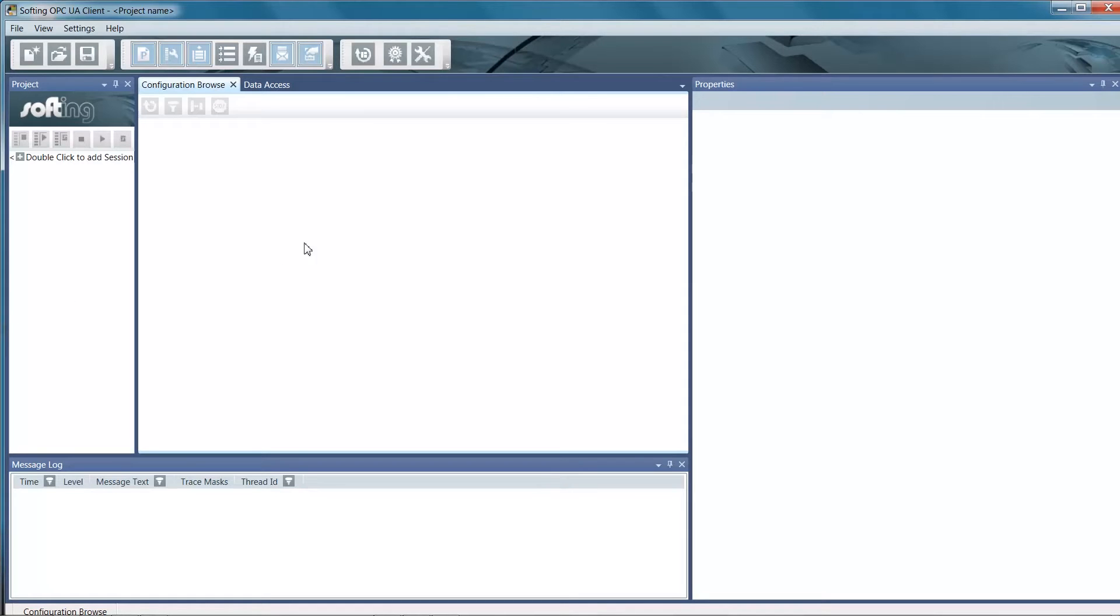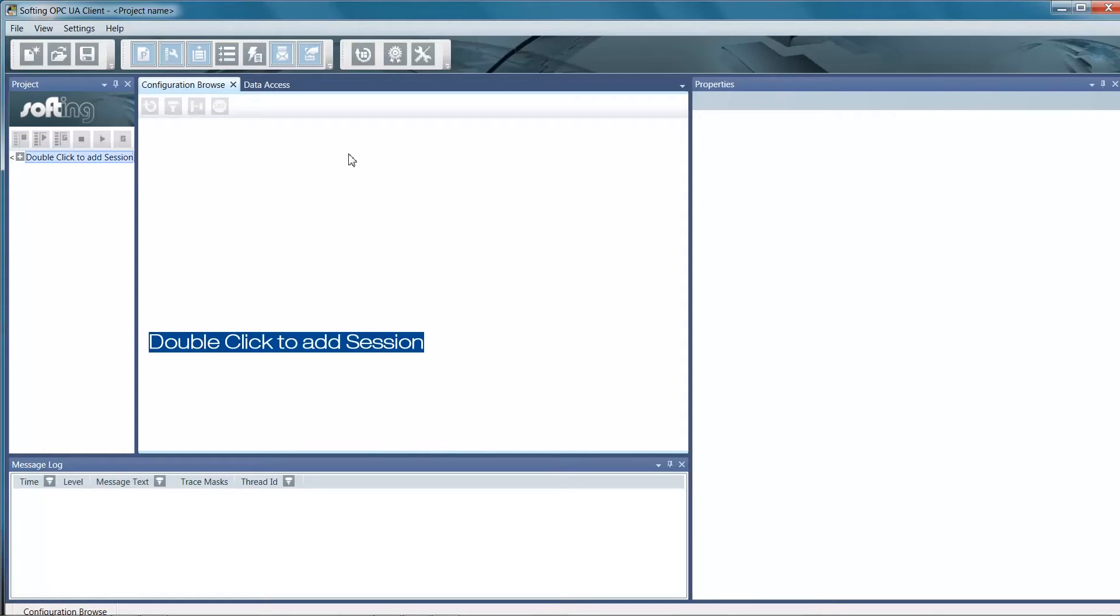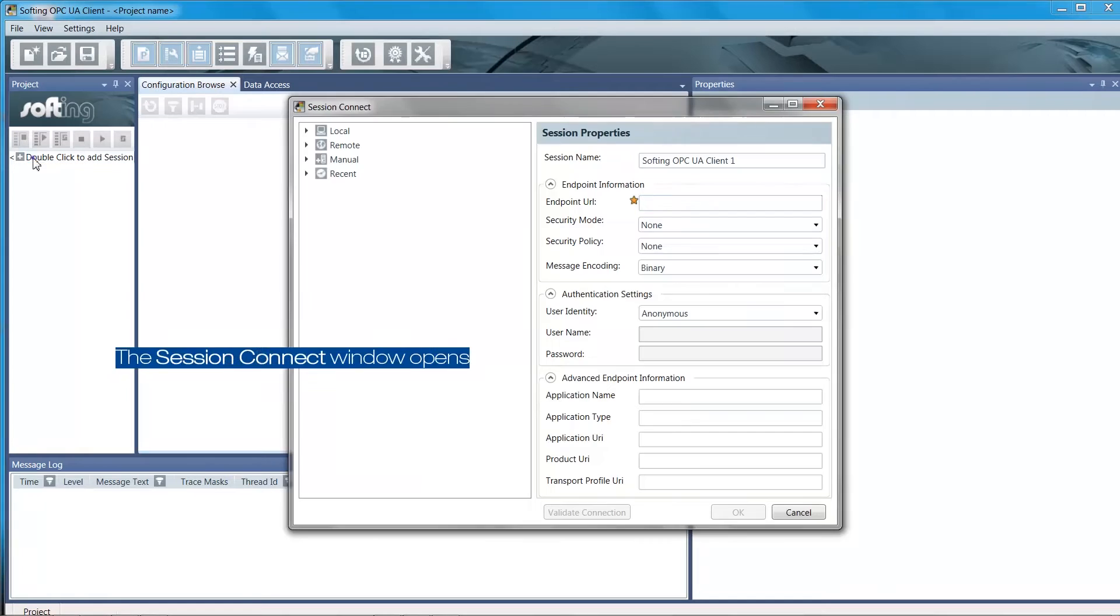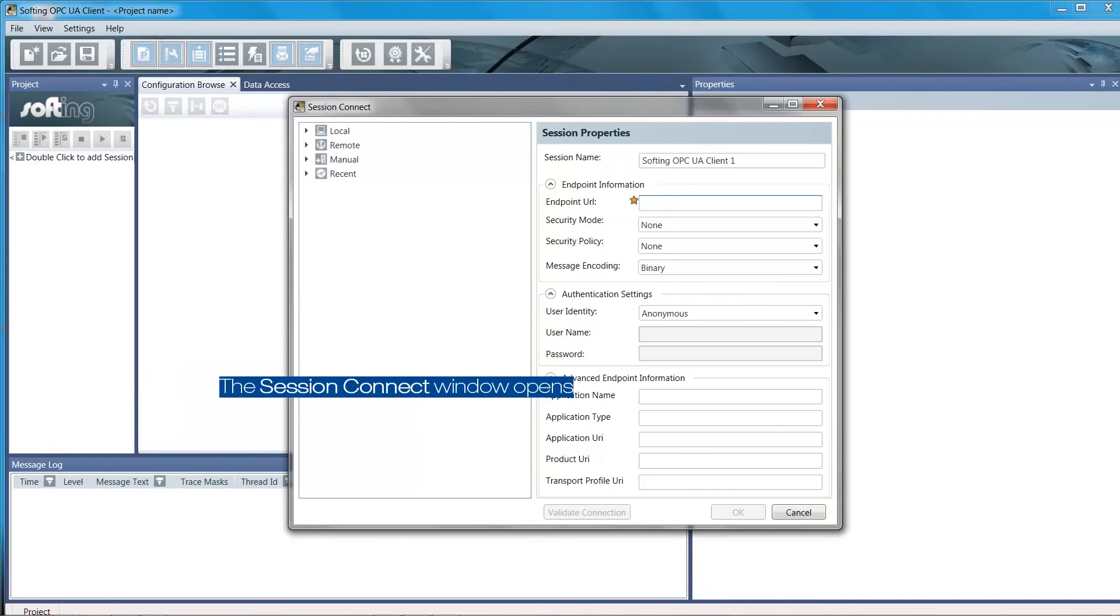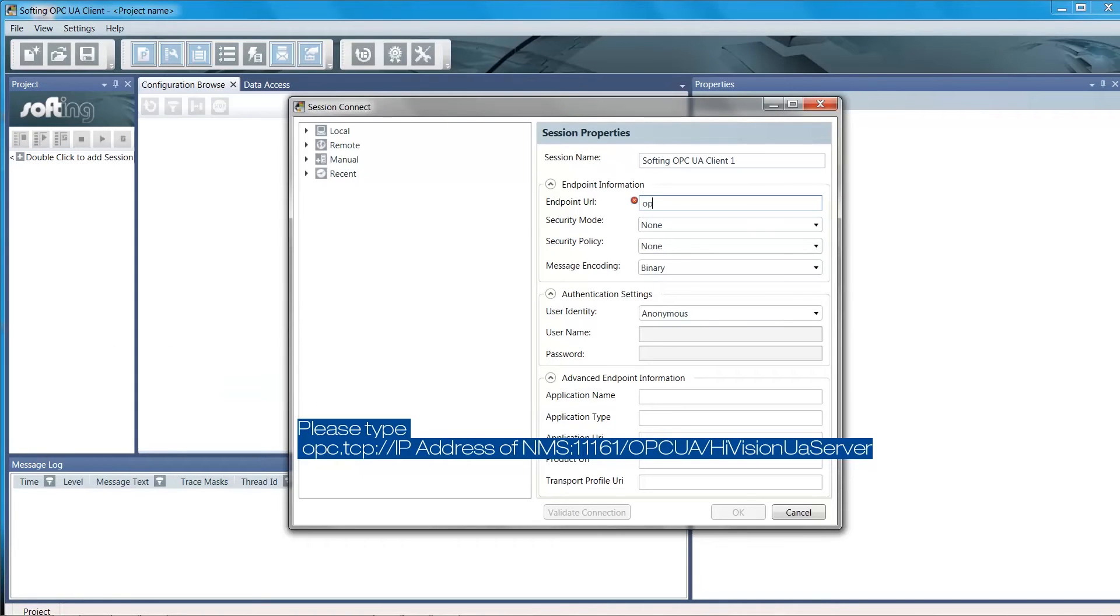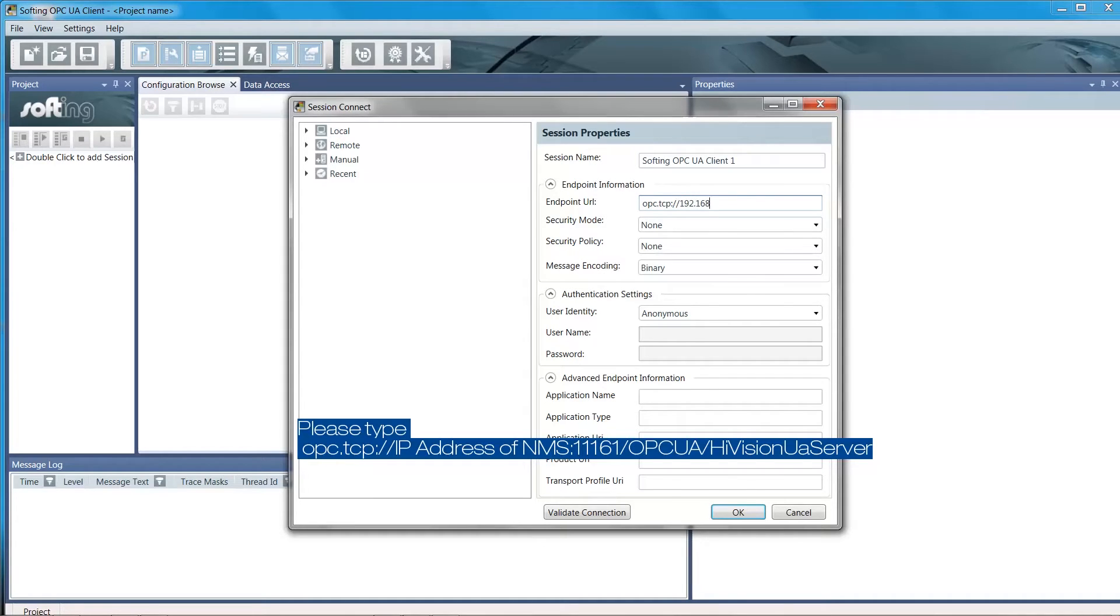The SCADA client needs to be configured in order to get the data from the HiVision server. Please double click to add the session. In the endpoint URL, please define the link as shown. The IP address is the HiVision server address, the port is 11161.